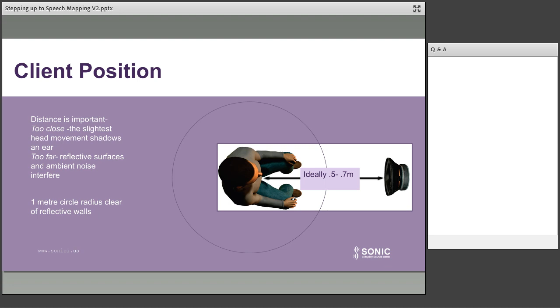Now, we do need to consider reflective surfaces. Ideally, there shouldn't be any hard surfaces within around a 1 metre radius circle. So make sure that you're not too close to your booth walls and things like that. Really try to get that client into a fairly free area and a free zone so you don't have any interference.